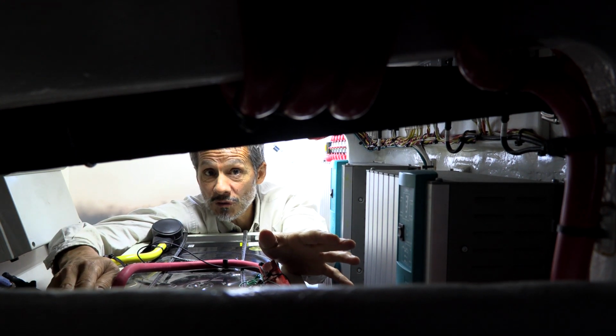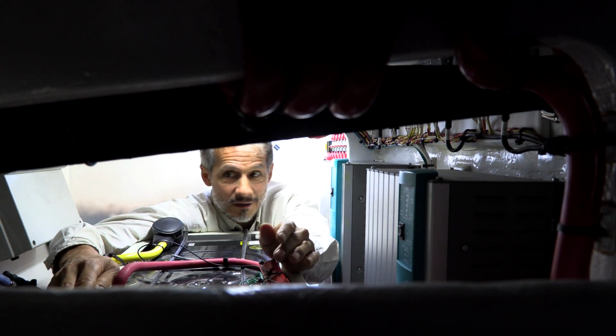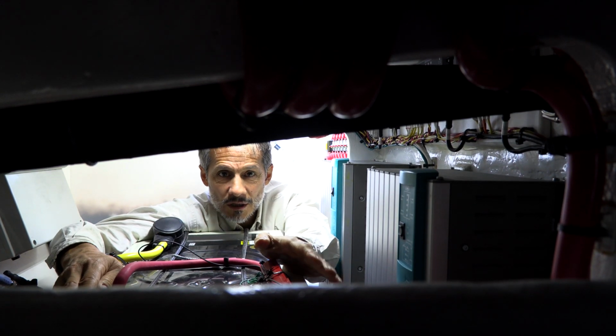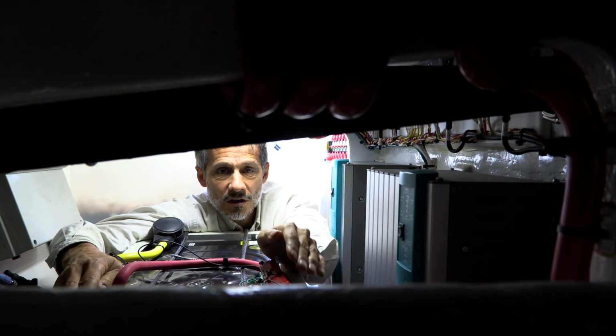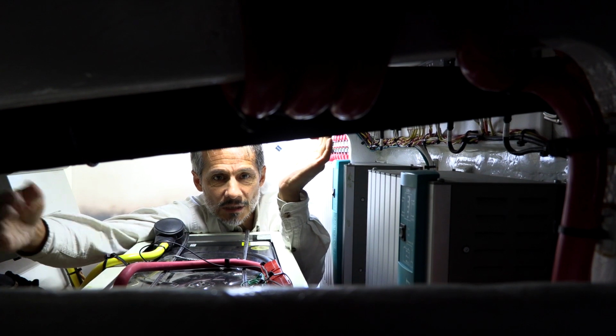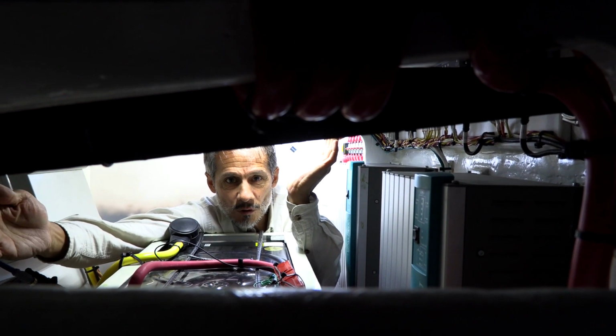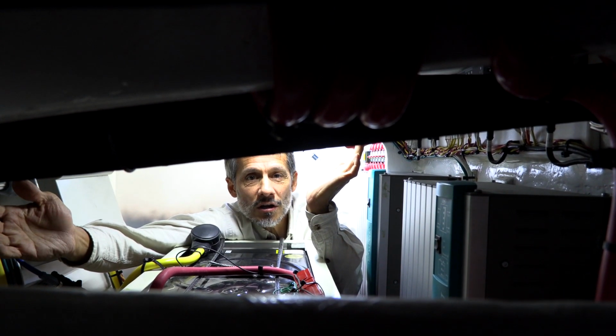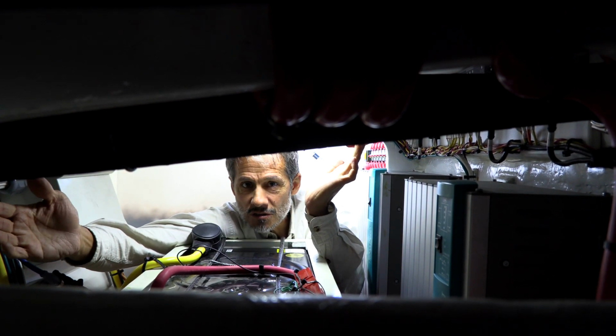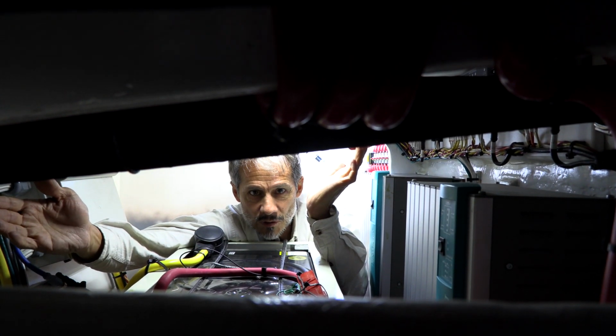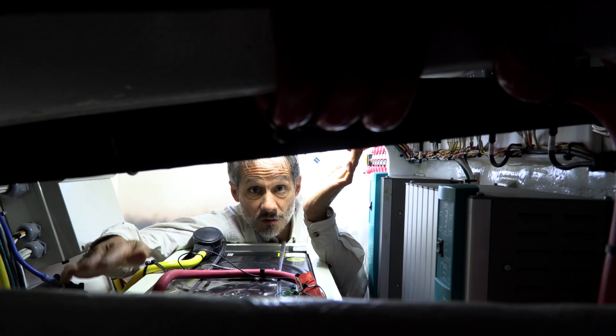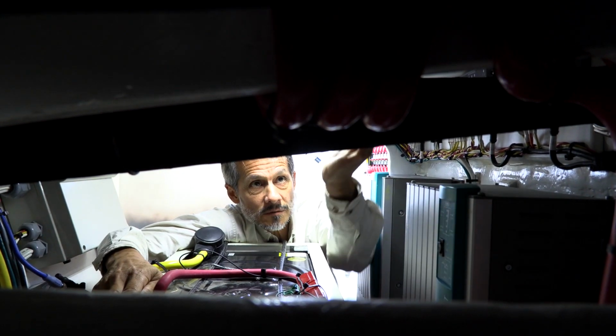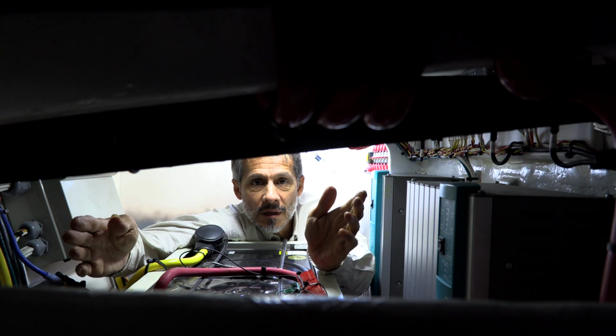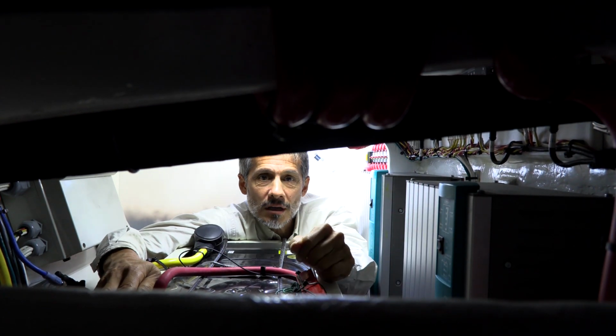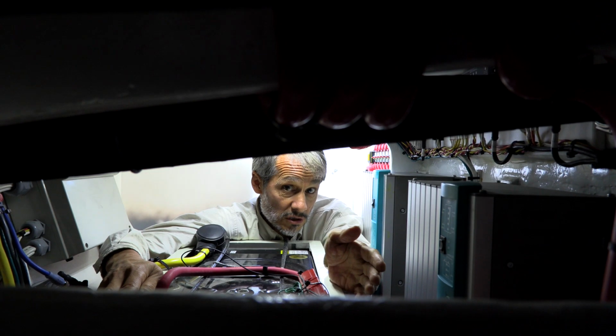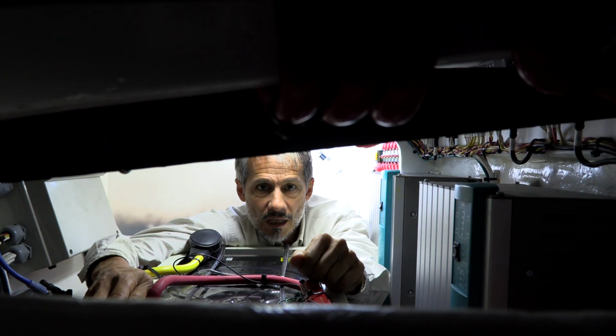Let's say you have a low voltage situation, where you've run the inverter down to a low state of charge. The BMS can cut off the load side but leave the charge side connected, so the solar panels stay connected to the boat. If you're not on the boat and it's an unintended situation, when the sun comes up, the solar panels start charging through the still-live charge bus connection, and when the voltage comes up, the system automatically turns the load side back on. This prevents the system from getting over-discharged and shortening the life of your batteries.